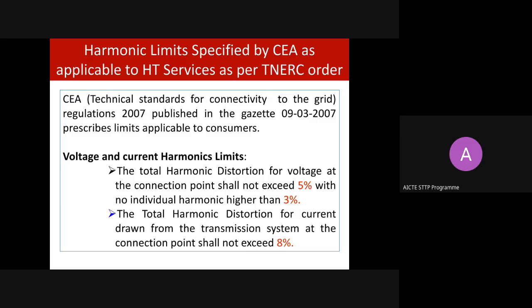If industrial premises maintain THD less than 5% and individual harmonics less than 3%, they will not be penalized. In the sense that they have to put appropriate filters in the premises to ensure THD is less than 5% and individual harmonics less than 3%. If it is more than the limit, they will be penalized by the utility. These are the norms fixed by the CEA, Central Electricity Authority.